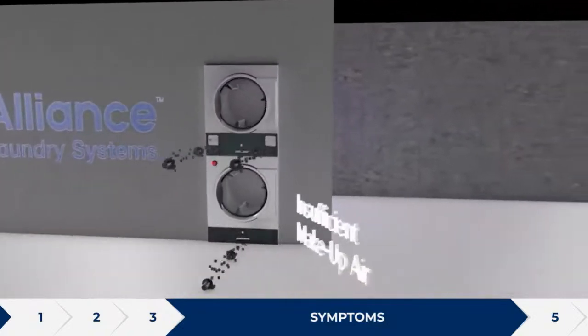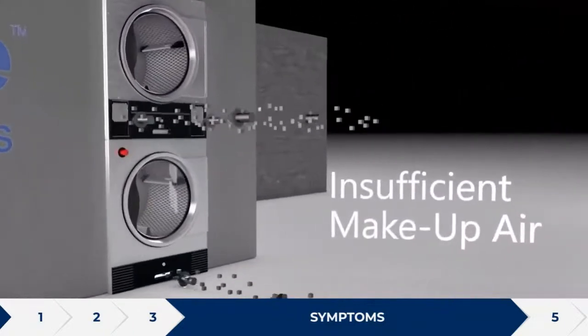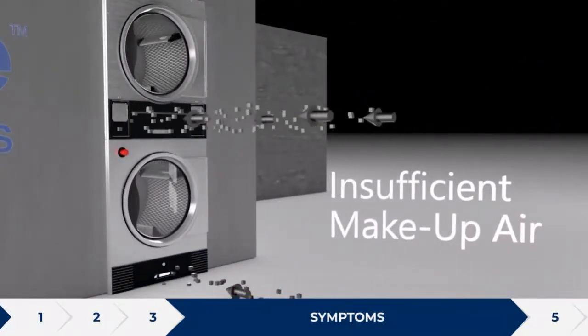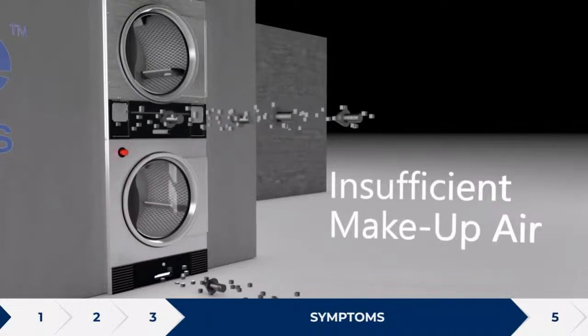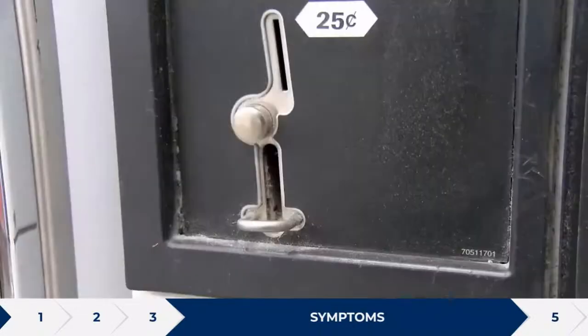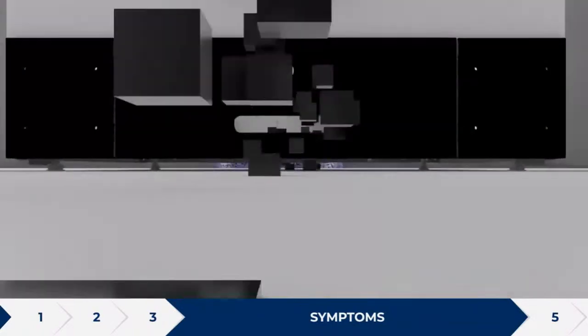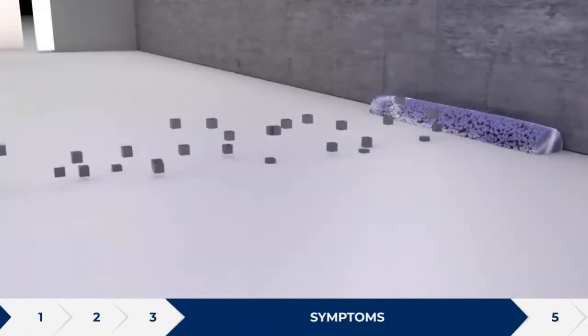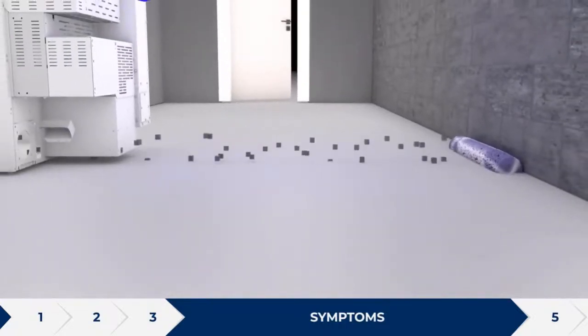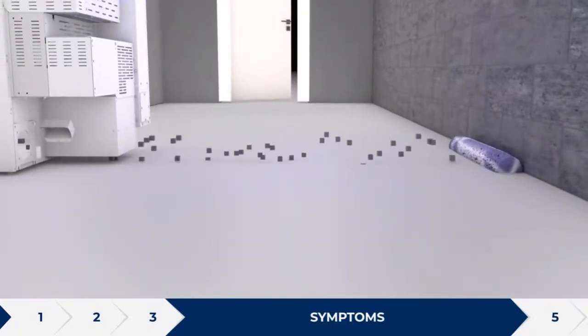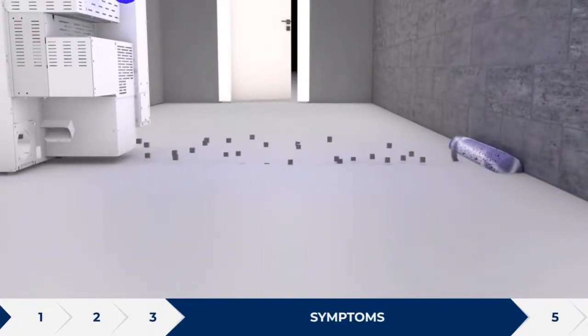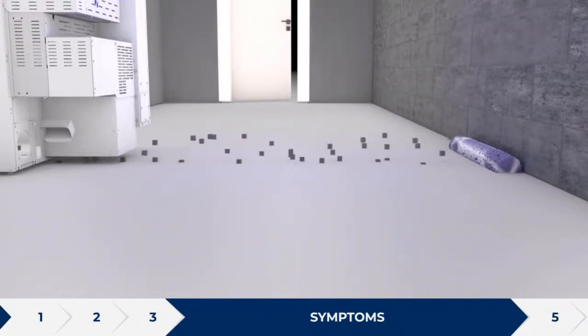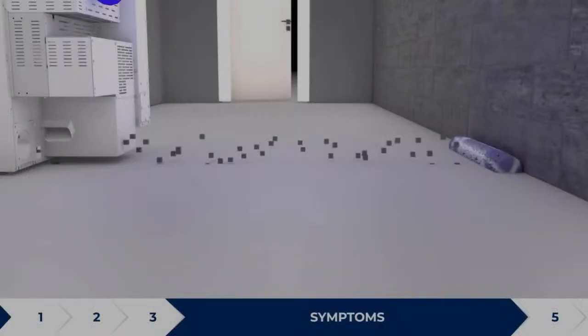When makeup air openings to the rear of the tumble dryers are insufficient, the tumble dryers will draw air from anywhere possible. This includes openings between other tumble dryers, through the control or coin drop, and the gap between the floor and the tumble dryer. A common visual result of a lack of makeup air is the accumulation of lint on the floor behind the tumble dryers that has been blown to the rear wall.